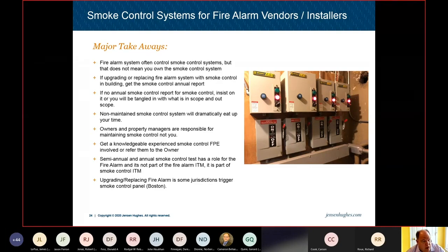So the owners and property managers are responsible for maintaining the smoke control systems. It's not your requirement, unless someone's paying you explicitly to test those smoke control systems as part of it. The smoke control system test is not part of the NFPA 72 minimum required test. So you want to get a knowledgeable, experienced smoke control fire protection engineer involved, or refer them to the owner. Maybe the owner's not doing this stuff, and maybe if you pass along or refer someone like a Jensen Hughes to an owner to get them to test out their system and get that properly set up and maintained, it will make that fire alarm system upgrade or replacement go a little smoother if you're dealing with smoke control.